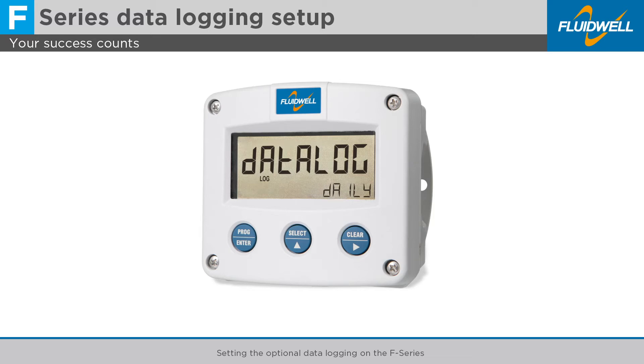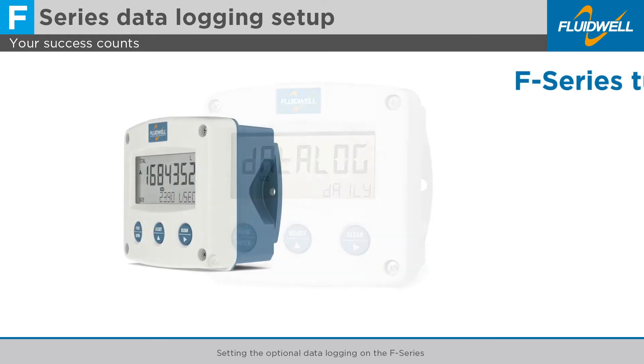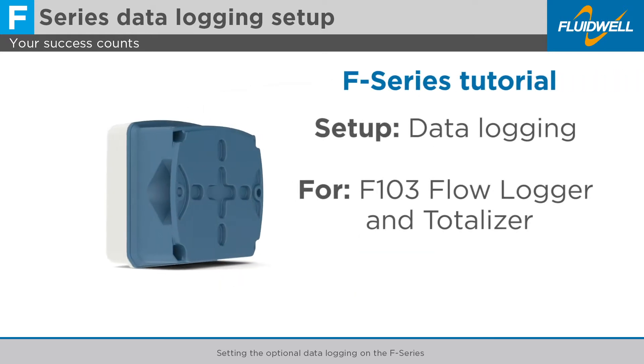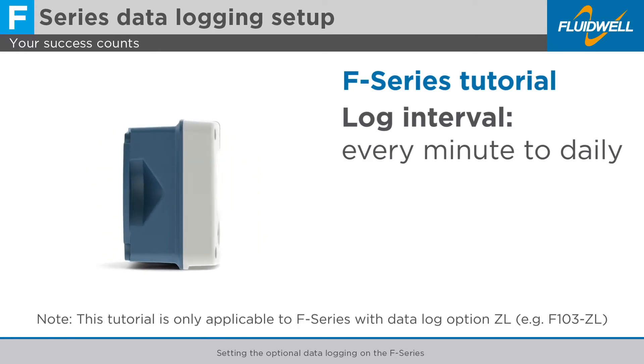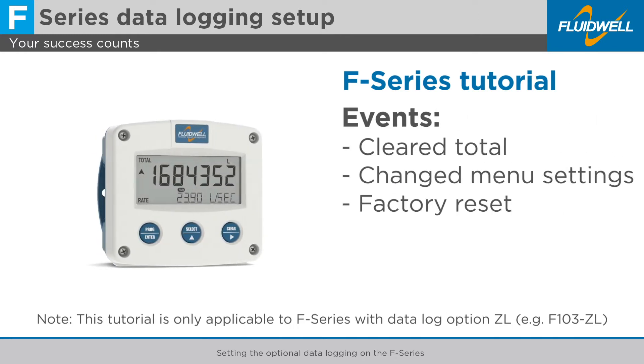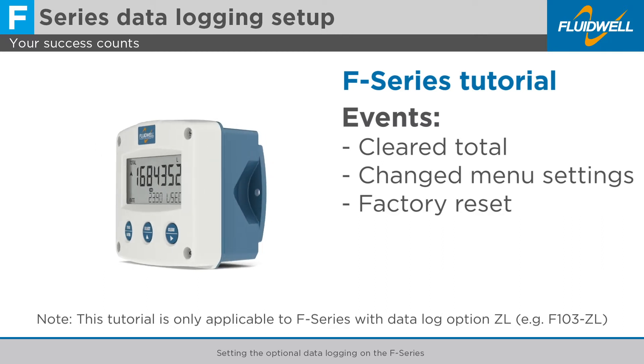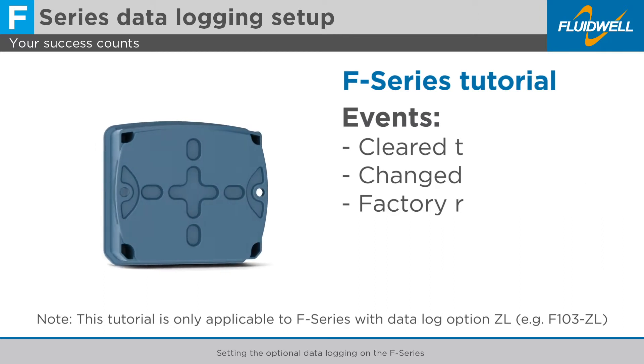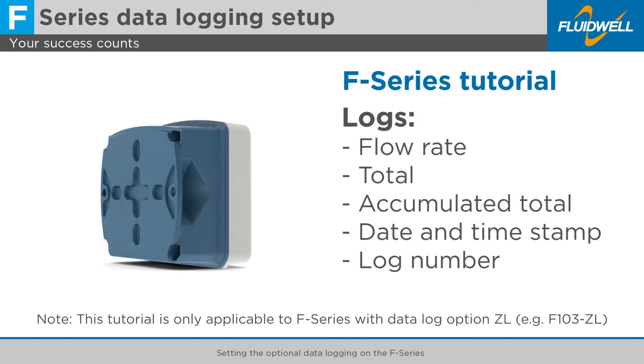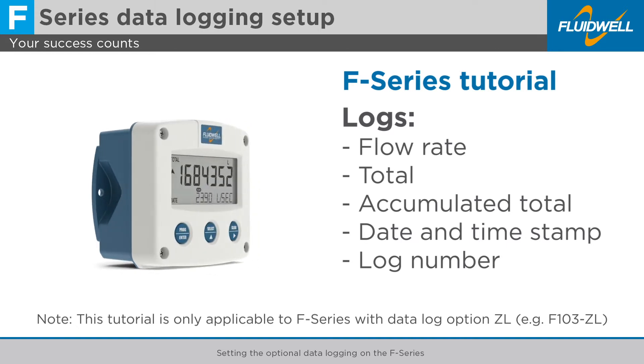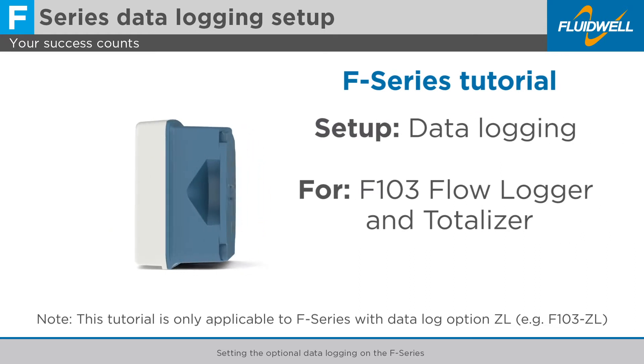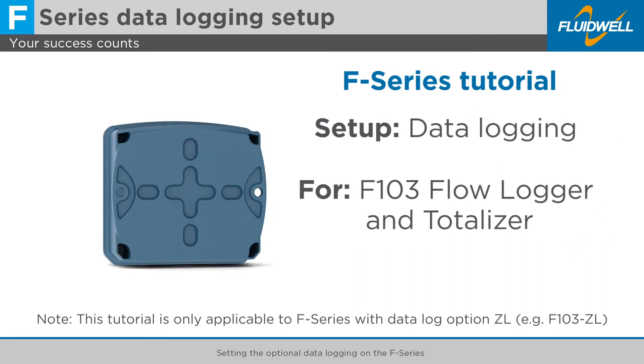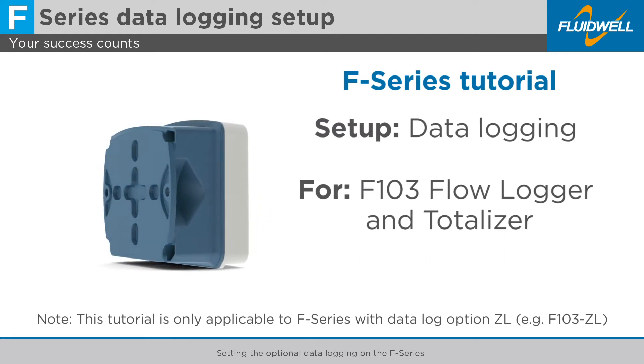When you need to easily monitor your flow measurements and historical data events over time, the logging feature on the F103 is the perfect tool for you. The log interval can be user-defined from every minute to daily. Events such as cleared total, changed menu settings, or factory reset can also be logged. Each log contains flow rate, total, accumulated total, date and timestamp, and log number. In this tutorial, we will show you how to set the optional data logging on the F103 flow logger and totalizer.